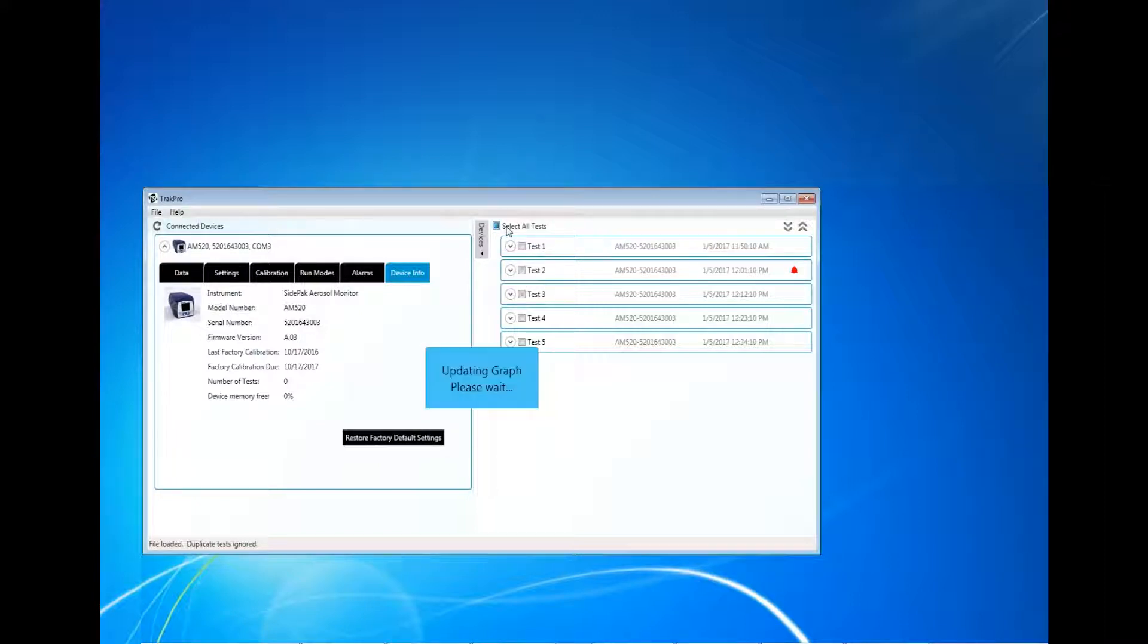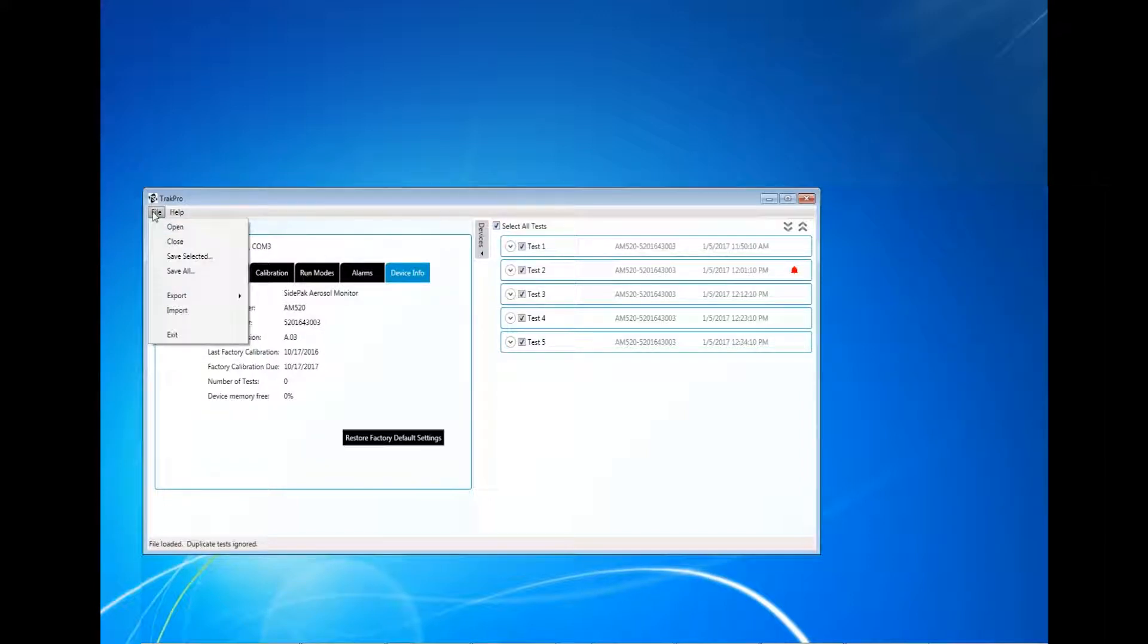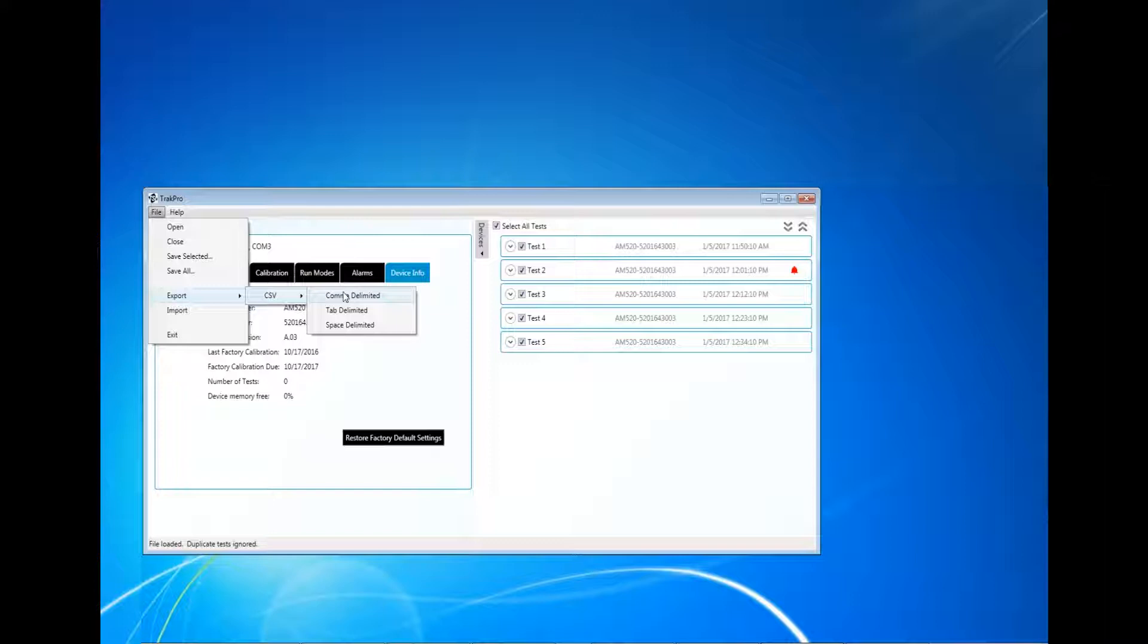To export test data to a CSV file, first select the tests you would like to export. Multiple tests can be exported, but they will all be contained in a single CSV file. After determining which test you would like to export, click File and navigate to Export in the menu tree. Select CSV and select the preferred delimited type. Comma delimited is the most common and will separate the data into individual cells.